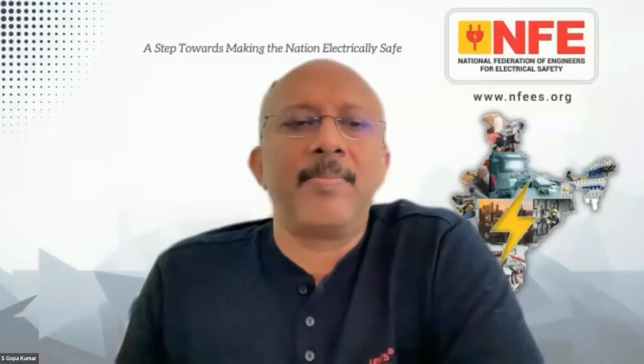Steam, sprinkler, stuff like that, yeah, we would probably still bond. Again, if they're extraneous, we test for it, because you're trying to mitigate the bringing in of hazardous voltages to ensure that you don't get a shock when you're making a cup of tea and leaning up against a radiator or a steel structure. But the gas one, I kind of do agree. I think with gas, maybe we need to do something with the pipes to take that out of the realms of bonding those pipes. It's an interesting one for debate, Chris.